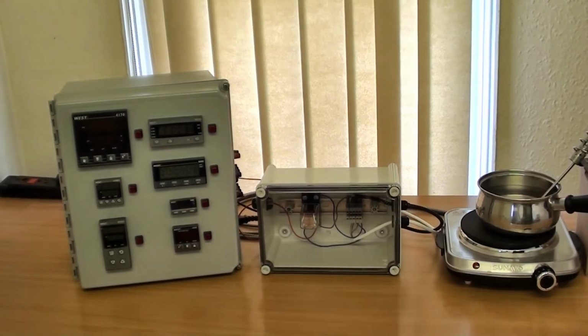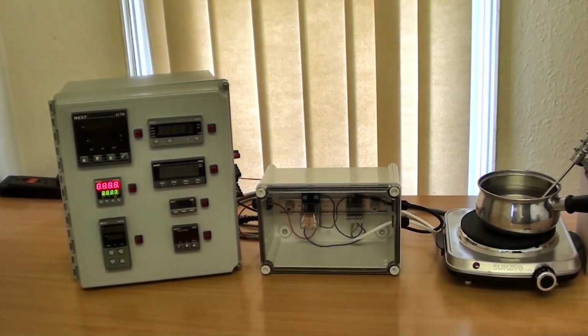I'll turn the controller on. The controller is at its factory default values. The proportional band is 10%, the integral or reset time is at 5 minutes, and the derivative time or the rate is at 1 minute 30 seconds.